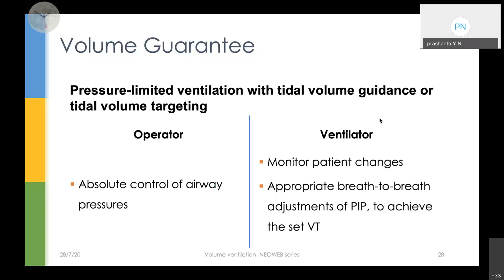As an operator, I have absolute control of airway pressures. We know that, right? I can set how much pressure I want. But what the ventilator does is monitor the changes at the patient end, and it looks breath to breath to see how much pressure I need to give to push a certain amount of air into the circuit. In subsequent slides, I'll make it a little simpler for you.